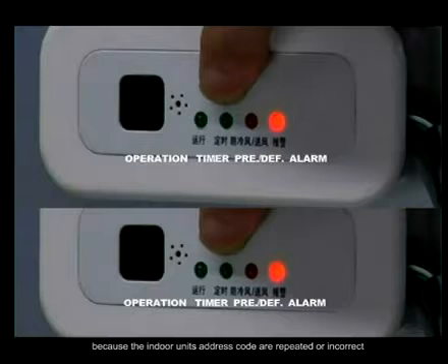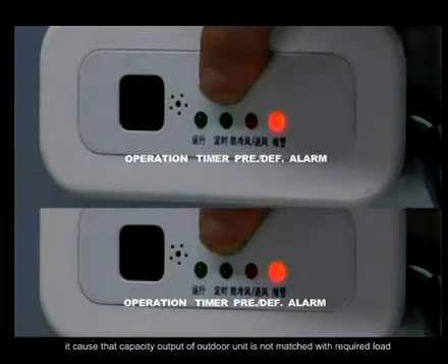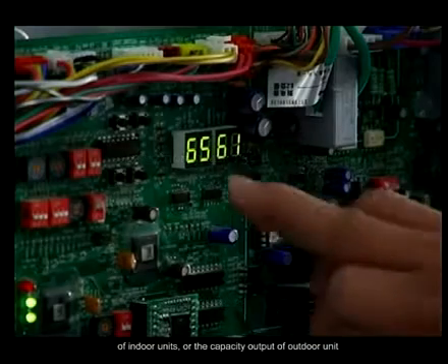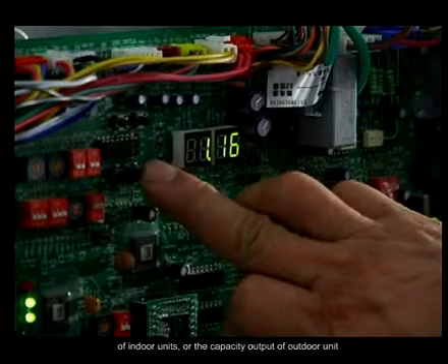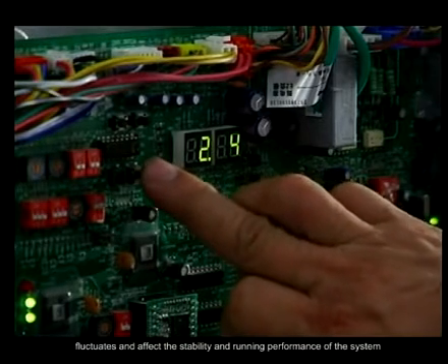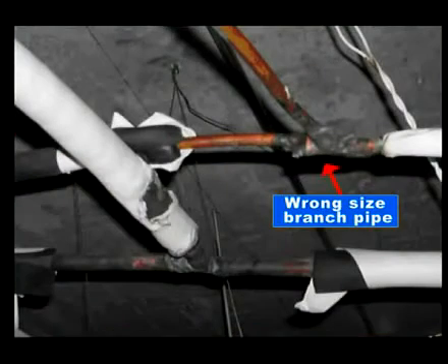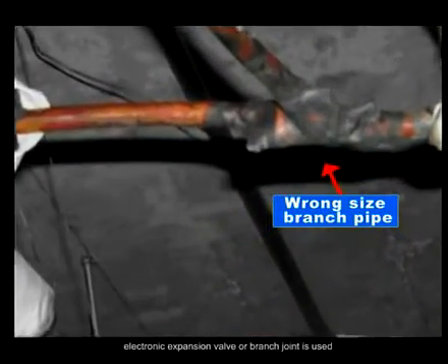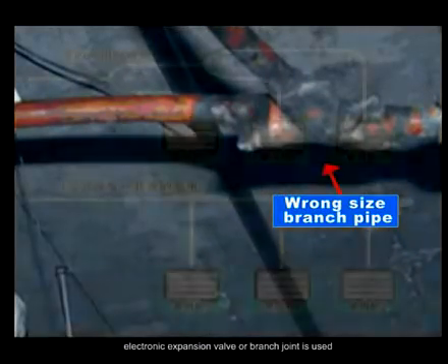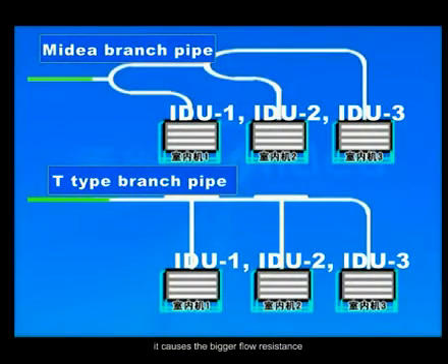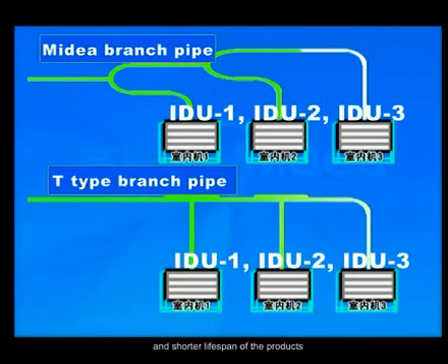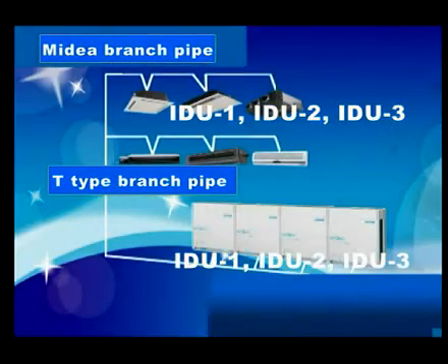Because the indoor unit's address codes are repeated or incorrect, the capacity output of the outdoor unit is not matched with the required load of the indoor units, or the capacity output of the outdoor unit fluctuates and affects the stability and running performance of the system. Because an improper pipe diameter, electronic expansion valve, or branch joint is used, it causes bigger flow resistance, unbalanced refrigerant flow among indoor units, and shorter lifespan of the products. If any of the above points exist, they can cause bad system operation performance. You must absolutely correct the mistake.